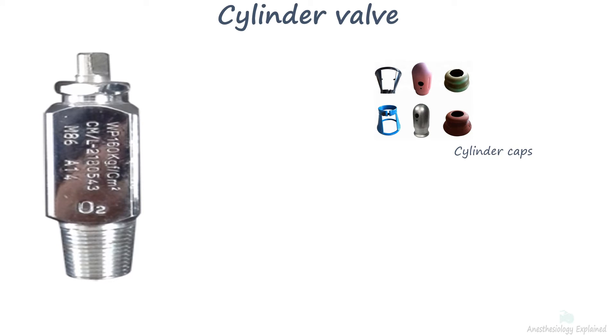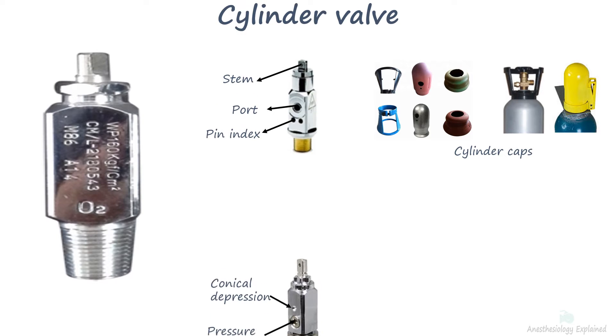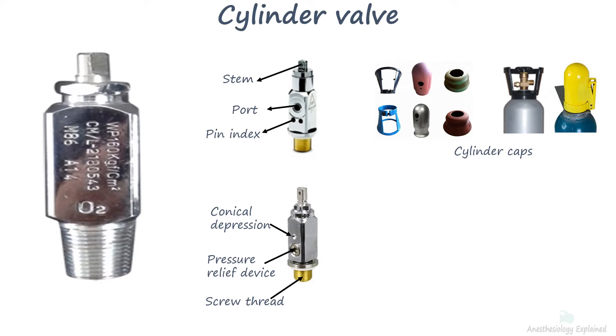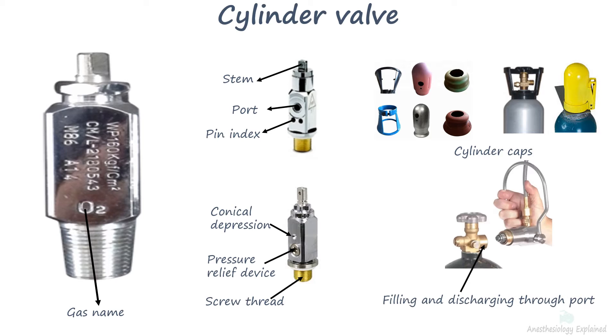The valve is made of bronze or brass and is the most fragile part of the cylinder, therefore provided with a metal protection cap to protect it. It has a port, stem, pressure relief devices, pin index safety system, conical depression, and screw thread. The chemical formula of the particular gas is engraved on the valve. Cylinders are filled and discharged through the valve, and the end of the valve is threaded to fit into the corresponding thread of the cylinder neck.